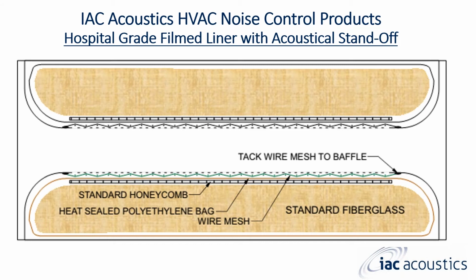This is really cool because it separates the heat sealed polyethylene bag that encases the fiberglass material. That way this does not stick to the perforated material. A lot of the people do not do this. This enhances the performance of our hospital grade silencer, number one. And number two, the heat sealed bag totally encapsulates the fiberglass material, so this keeps any type of fiberglass material from being emitted into the system. This is very critical for hospital grade type silencers.